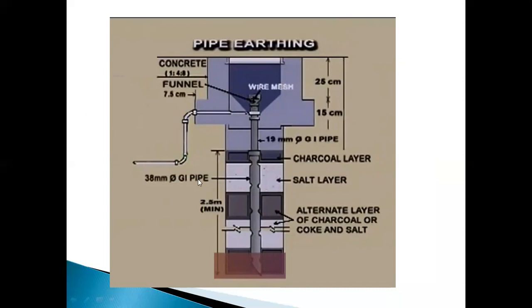It is a method. In the pipe earthing method, here we are going to observe a 38 mm diameter galvanized iron pipe of approved length of 2.5 meters placed vertically downwards in wet soil. If the soil is dry and rocky, the length of the pipe should be increased to 2.75 meters. The inclination of the pipe, if you observe here, should not be more than 30 degrees with respect to vertical. Should not be more than 30 degrees.